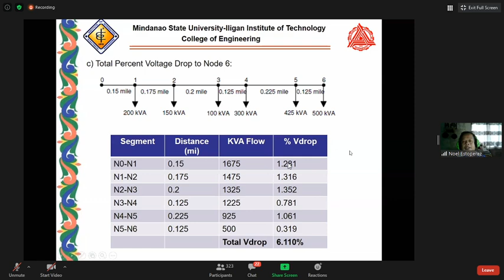So if we look at our Philippine Distribution Code, this passes, because the variation we mentioned is plus or minus 10%. So this is within the 10% variation. So this is simply an alternative way of finding the percent voltage drop for our distribution network.